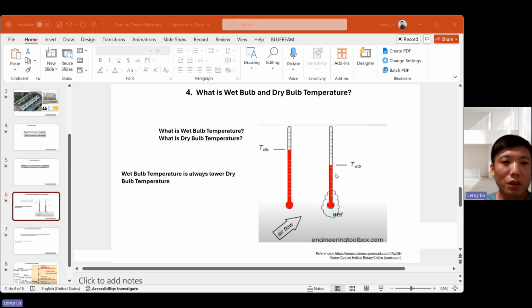So moving on, let's talk about the wet bulb temperature, WBT. This is a very important concept. Wet bulb temperature is the lowest temperature to which air can be cooled by the evaporation of water into the air at constant pressure. We are trying to cool the water by giving it more air to take the heat out of the water. That's the basic concept.